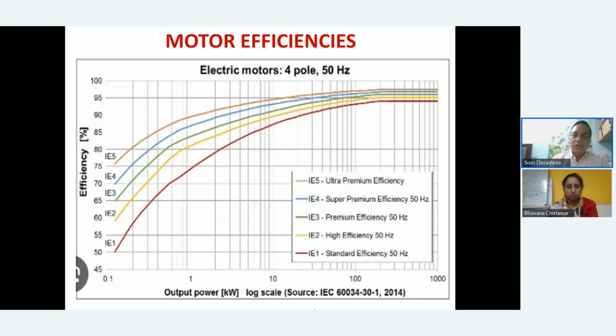And of course, now you have those lower horsepower motors, all those less than 10 horsepower. If you replace them, from 85 to 95, 10% just by changing the motor, you can improve. I think the paybacks are fantastic. So for lower horsepower motors, please take a bulk decision. You can sell off these running motors, take some money out of the salvage value, and replace them to get an attractive payback period.